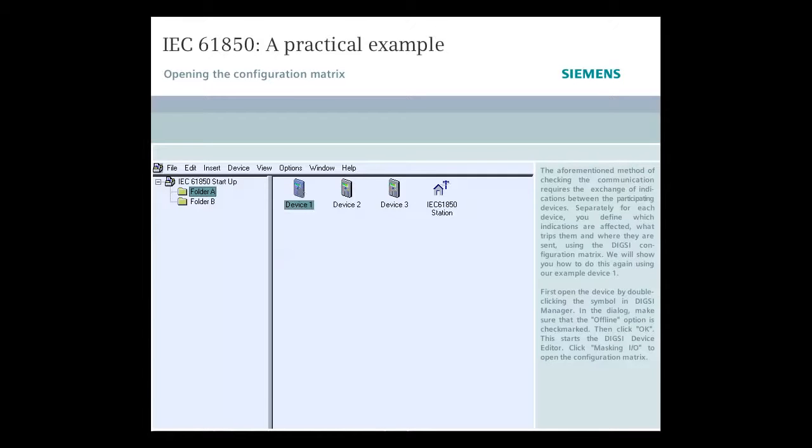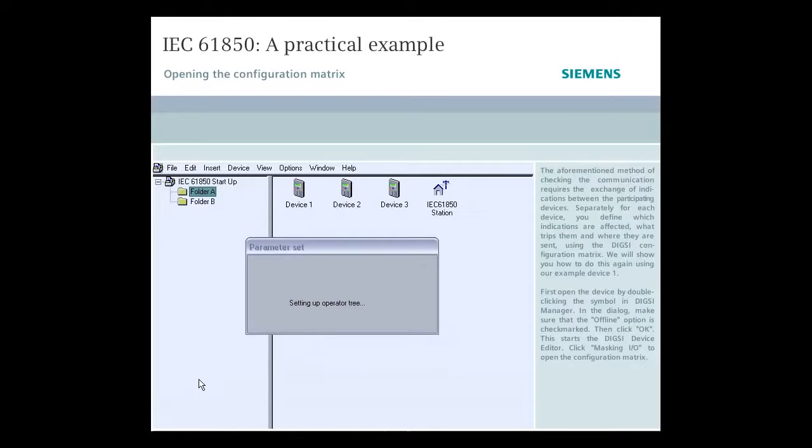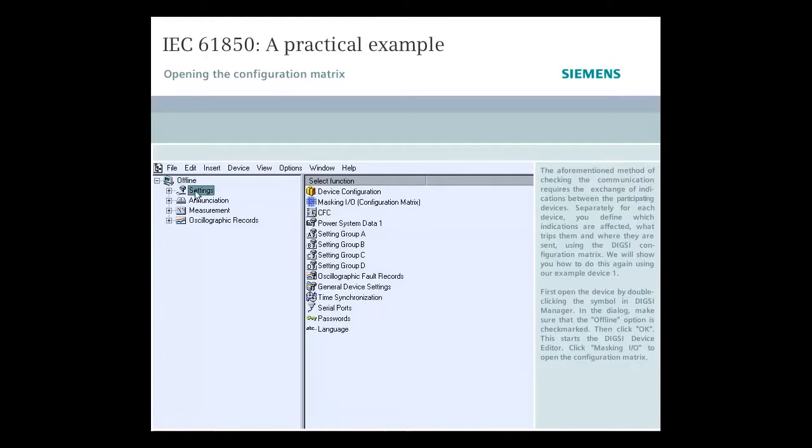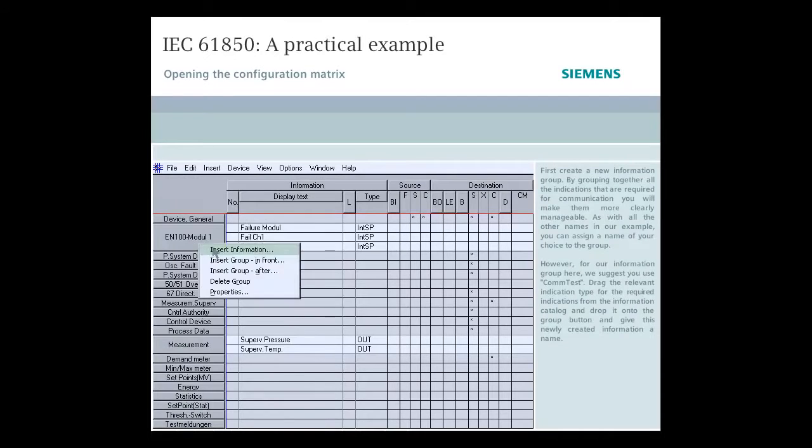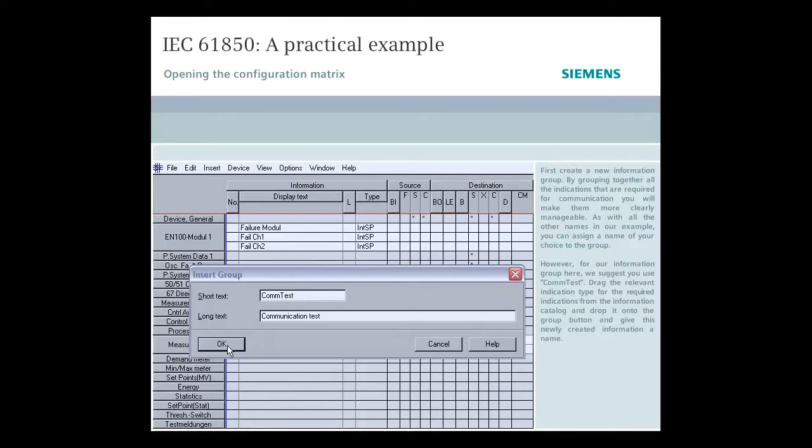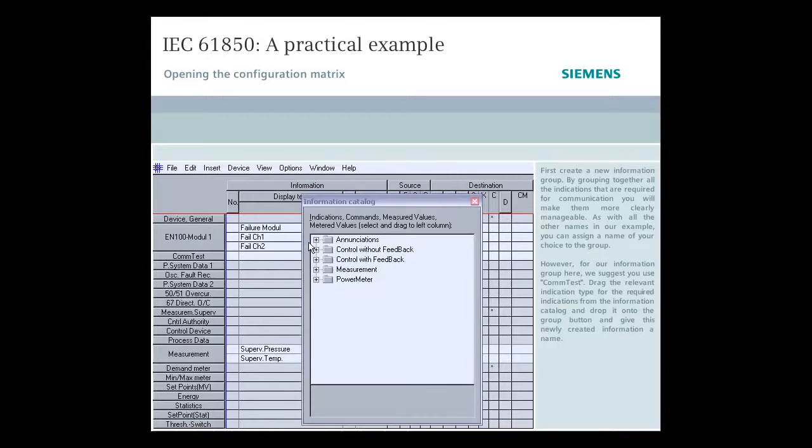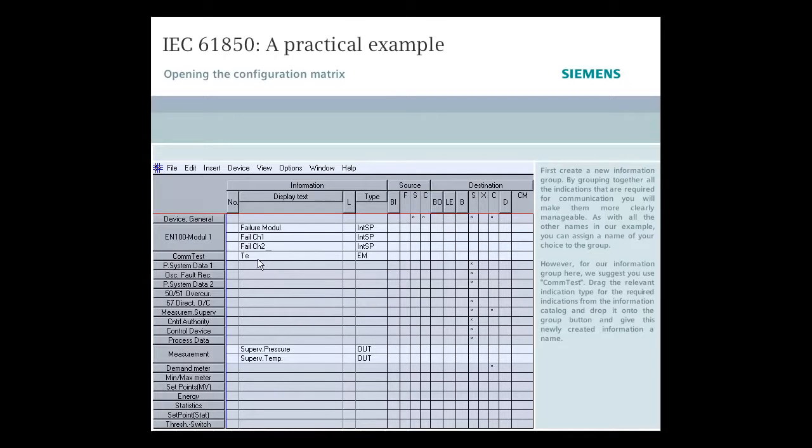First, open the device by double-clicking the symbol in DIGSI Manager. In the dialog, make sure that the Offline option is checkmarked. Then click OK. This starts the DIGSI device editor. Click Masking I.O. to open the configuration matrix. First, create a new information group. By grouping together all the indications that are required for communication, you will make them more clearly manageable. As with all other names in our example, you can assign a name of your choice to the group. However, for our information group here, we suggest you use Com Test. Drag the relevant indication type for the required indications from the information catalog and drop it onto the group button and give this newly created information a name.